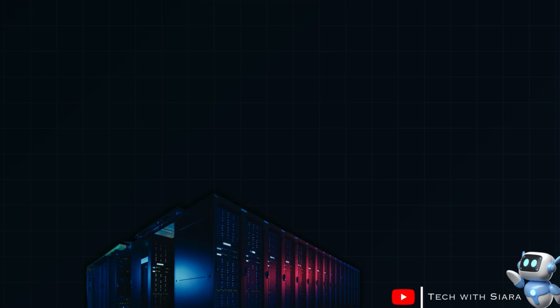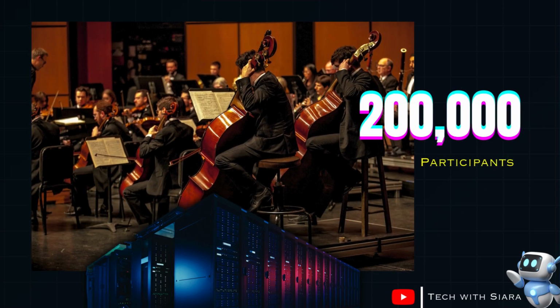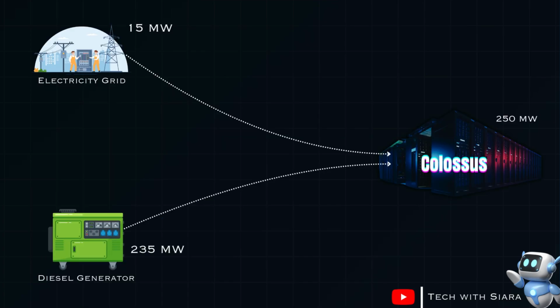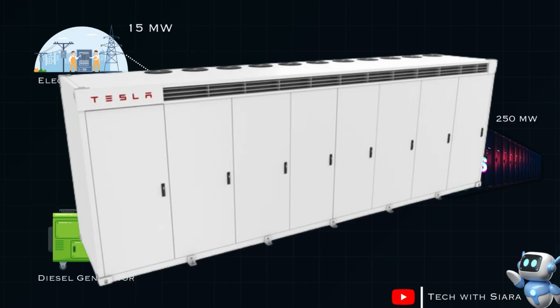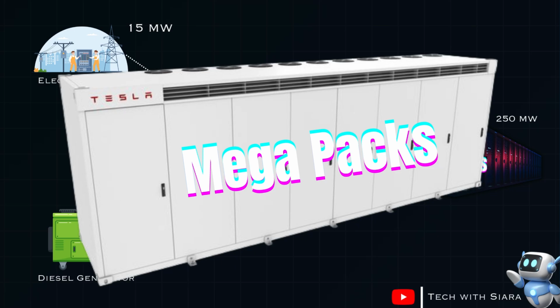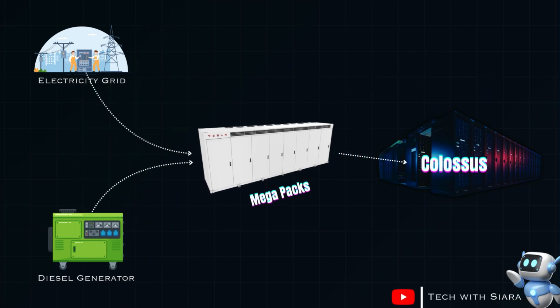This supercomputer is like a symphony of 200,000 participants. When all these GPUs start and stop within milliseconds, there are huge fluctuations in the power supply, which can damage the generators and the power grid. To solve this, xAI reprogrammed Tesla's battery system, called Megapacks. All the power from the grid and generators is used to charge these huge batteries, and the cluster uses power by discharging the batteries. This prevents any damage to the grid and generators due to power fluctuations.